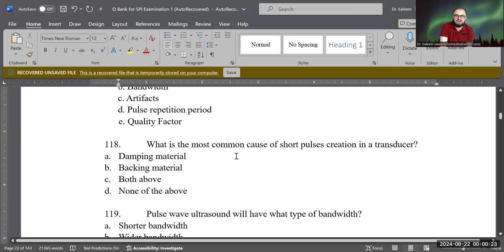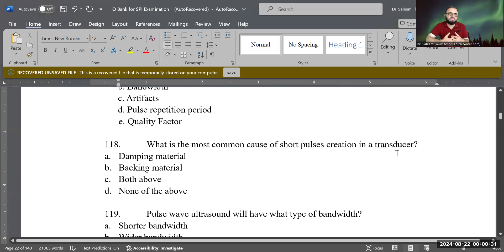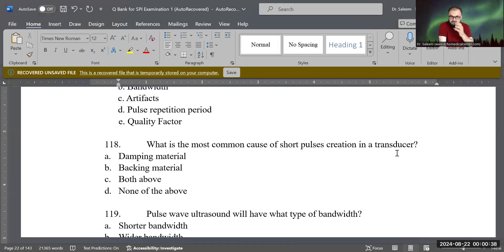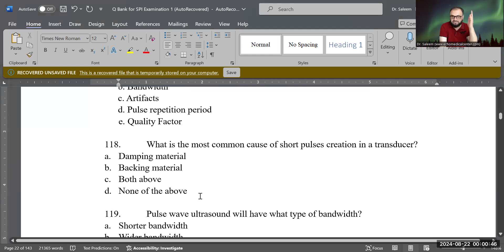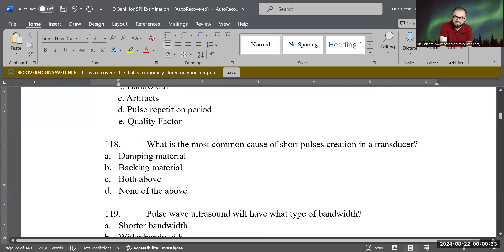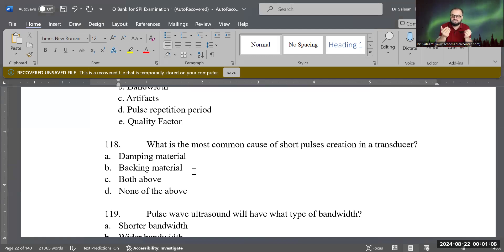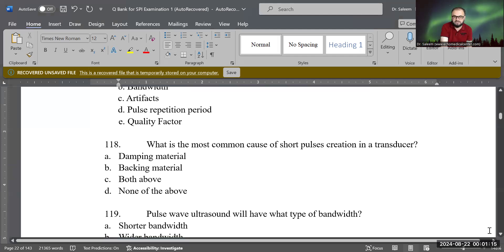What is the most common cause of short pulse creation in a transducer? How can you make a pulse shorter with fewer cycles? Options: damping material, backing material, both of them, none of them, or something else? Both damping material and backing material — they sit behind the crystal like a metal powder — absorb the continuous sound and shape it into short pulses. The more damping and backing material, the shorter the pulse and fewer cycles created. Both are correct.